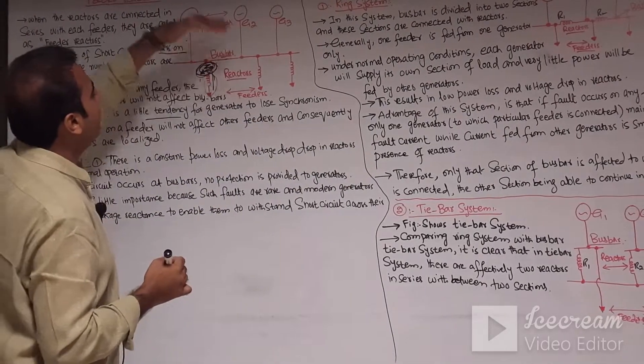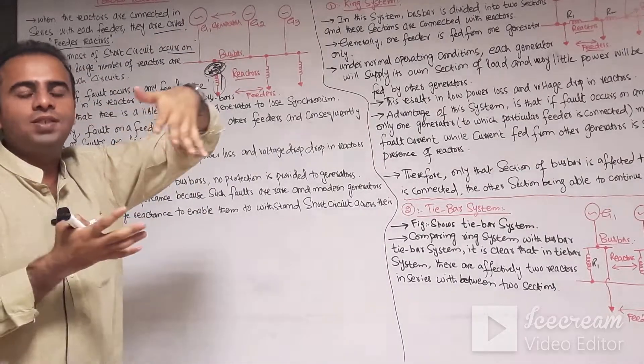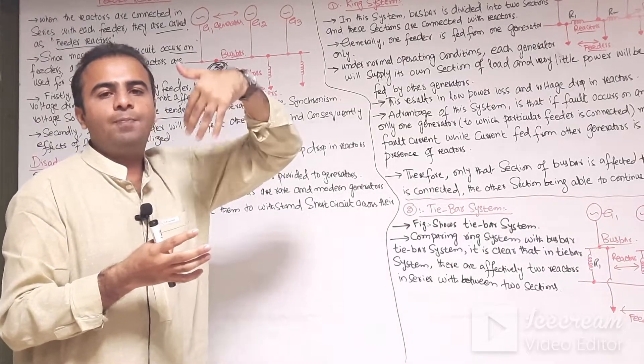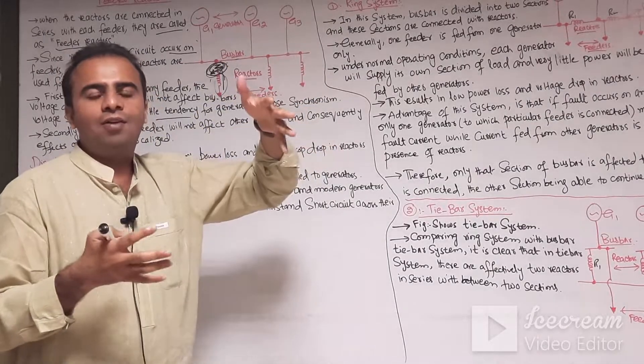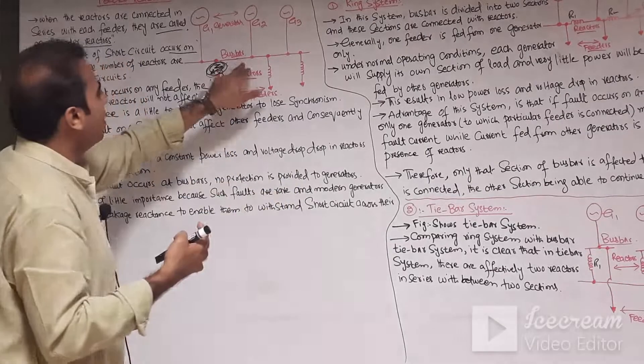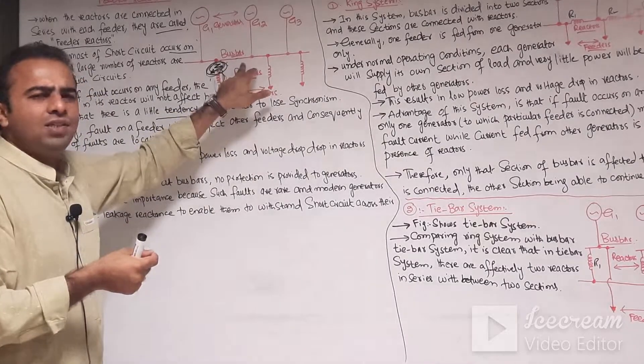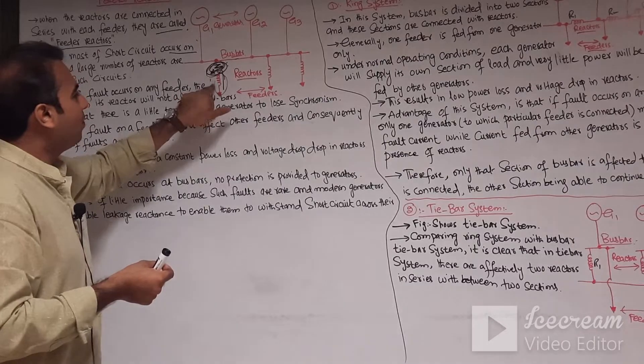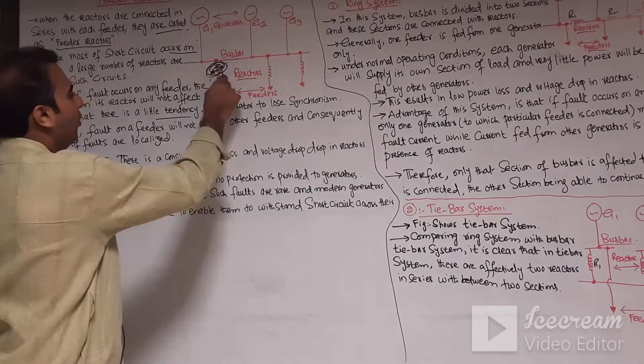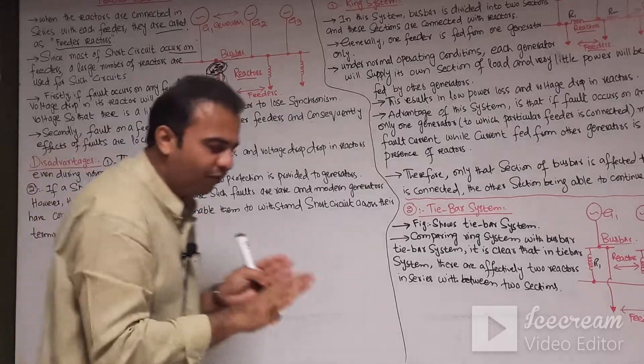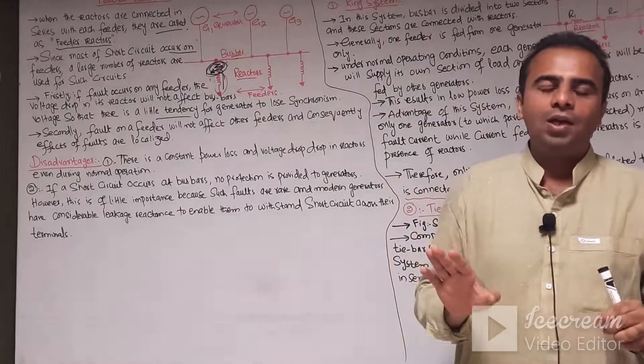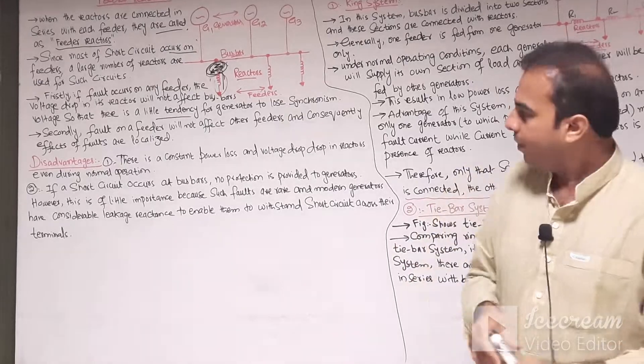Since the bus bar voltage is not affected, generators G1, G2, and G3 supplying that bus bar will not lose synchronism. Synchronization is the process where parallel generators connected with the bus bar must have the same voltage, same frequency, and same phase sequence. Because the reactor connected in series with the feeder limits the short circuit current, the bus bar voltage is not affected and the generators will not lose their synchronism.